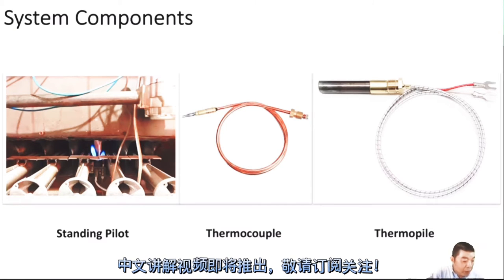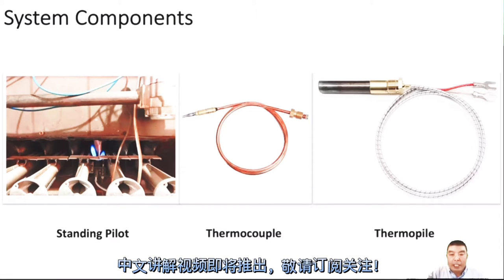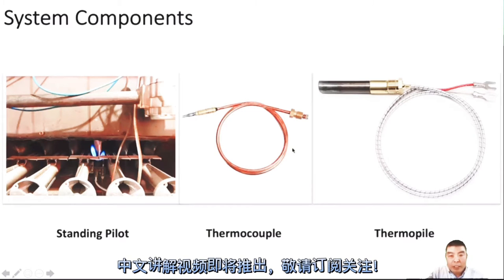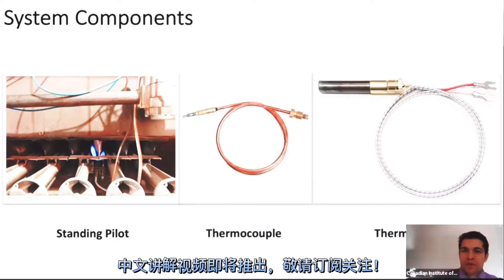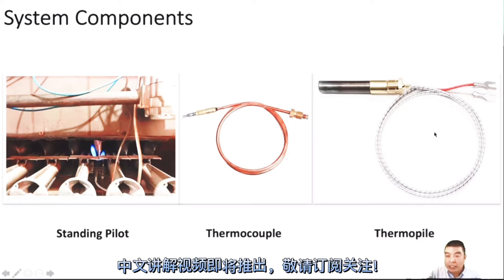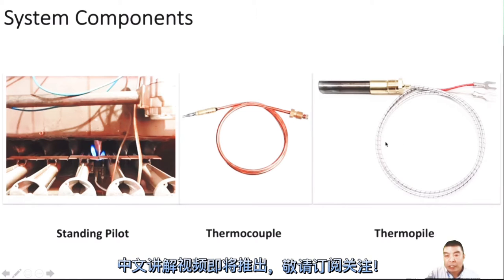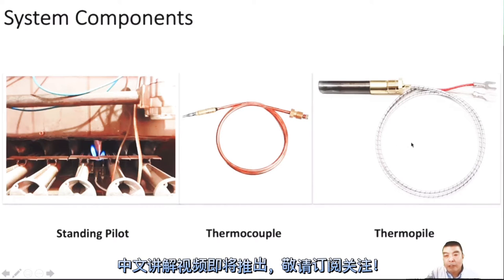The thermopile has the same function as the thermocouple, but the difference is it generates a different voltage. A thermocouple generates about 30 to 50 millivolts, while a thermopile generates about 500 to 750 millivolts — a big difference. We use the thermopile for the fireplace. Sometimes the fireplace uses both; I'm not sure why they use both, but sometimes we see both there.